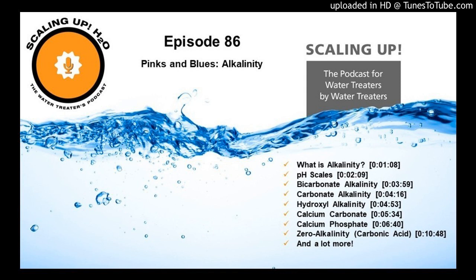Now, from the pH show, you know that a chef needs 5 ingredients in order to make scale, and those were calcium hardness, alkalinity. Hey, here you go, we're talking about alkalinity, pH, total dissolved solids, and temperature. So that's why alkalinity is so important, because it actually combines with our calcium hardness to create that scale, specifically calcium carbonate, which is the water treater's nemesis. It is the hardest thing for us to control because we are water treaters that deal with transferring heat from one place to another.